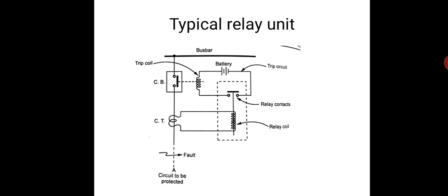During normal condition, the current is flowing through the relay coil, and whenever current flows through it, this coil gets electromagnetically energized. Can you see the upper part? This will pull the upper rod down. That is because whenever the current flowing through this relay coil exceeds the normal value, the relay coil contacts will get closed.